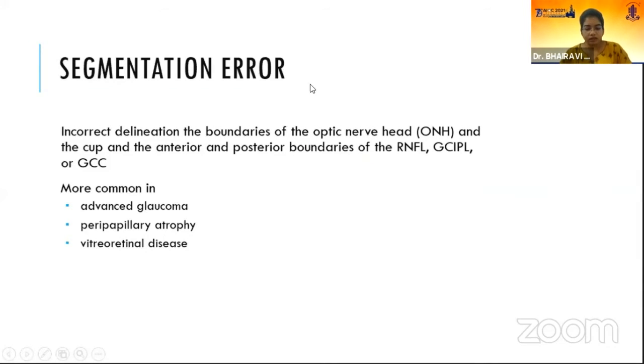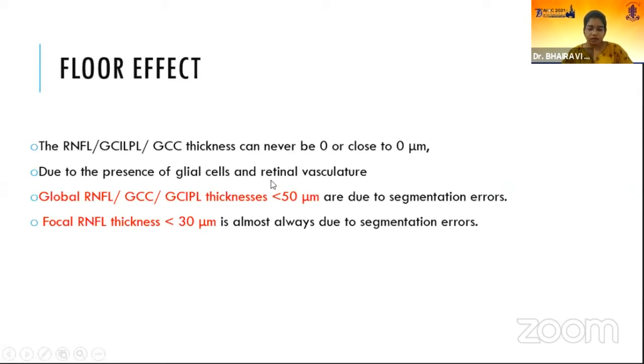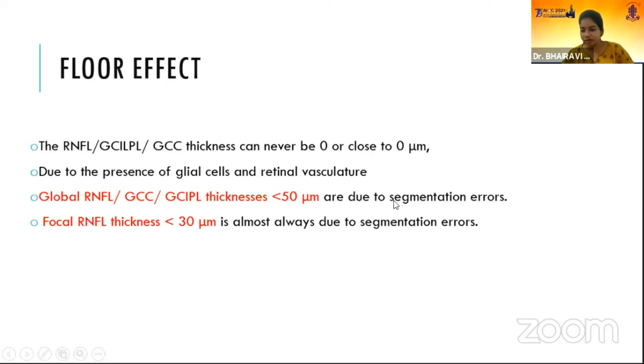Segmentation error is caused by incorrect delineation of the boundaries of the optic nerve head and the anterior and posterior borders of RNFL, GCIPL, and GCC. It is more common in advanced glaucoma, peripapillary atrophy, and vitreoretinal disease. The RNFL thickness can never be zero or close to zero due to the presence of glial cells and retinal vasculature even in advanced glaucoma. Hence, a global RNFL or GCIPL thickness less than 50 microns is always due to segmentation error, and a focal RNFL defect of less than 30 microns is always due to segmentation error.